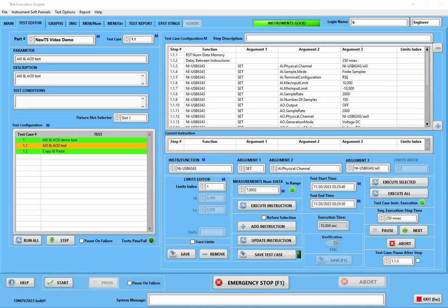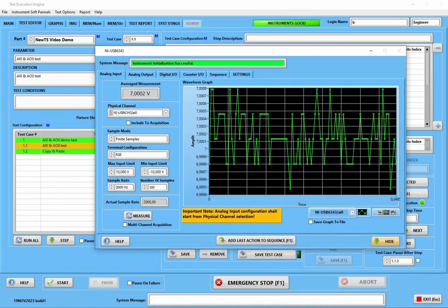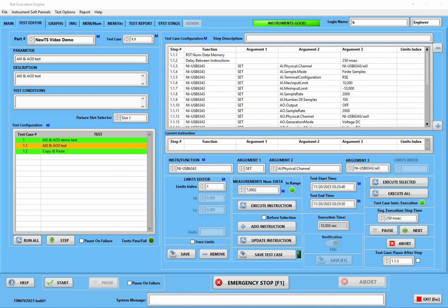It is the same as manually setting a real instrument. Because of that, instrument manufacturers came up with such features as save and recall the instrument settings. Since it is the internal functionality of the instrument, it executes much faster than via VISA or any other interface. Since we are using soft panels, we have an opportunity to generate the instruction sequence much faster.